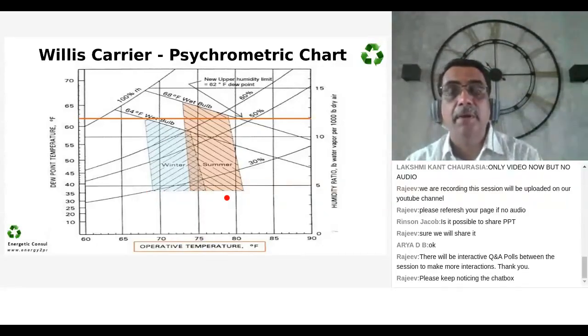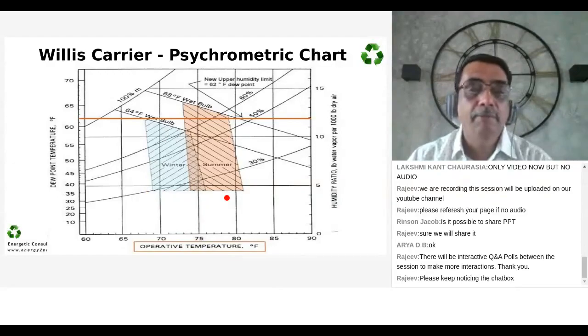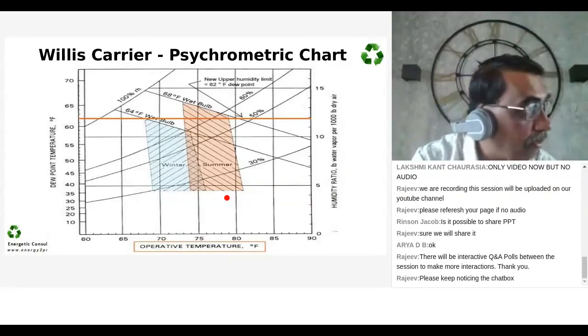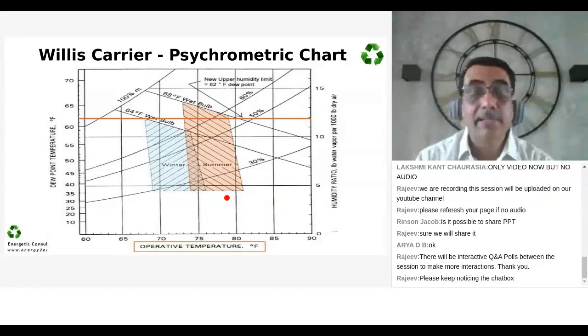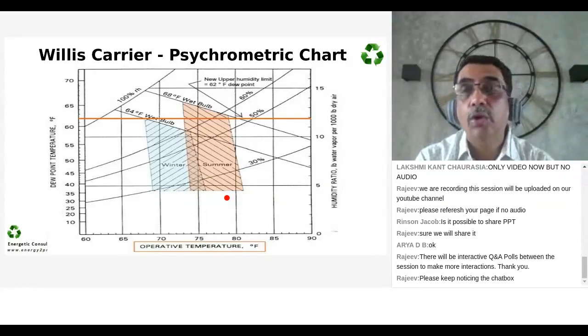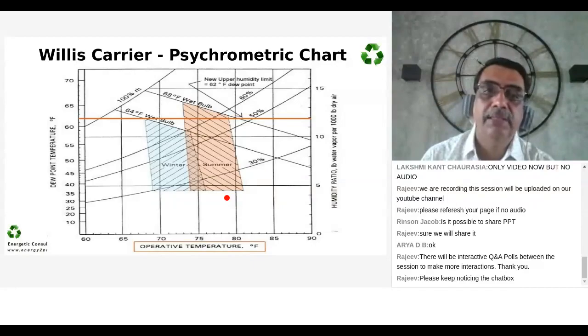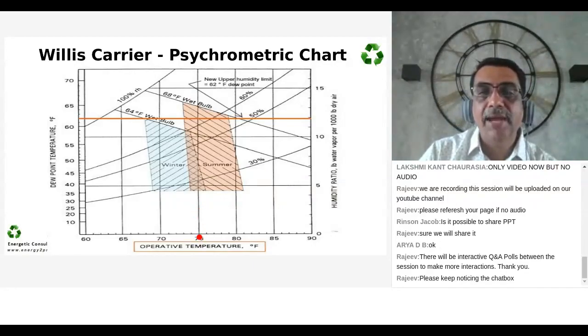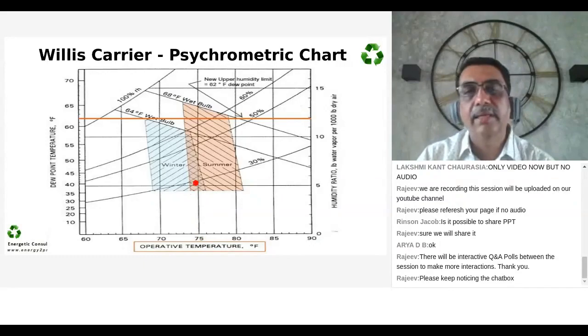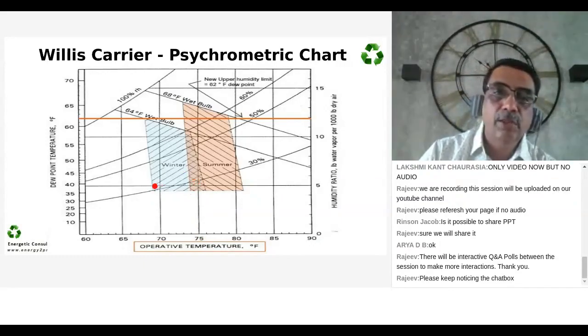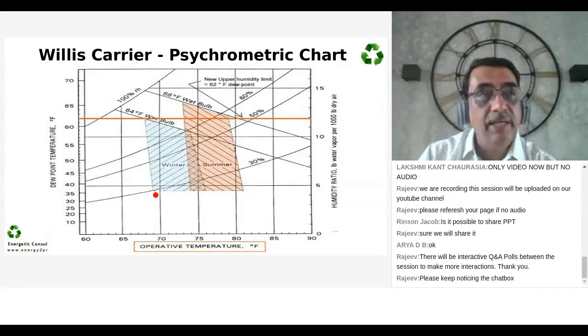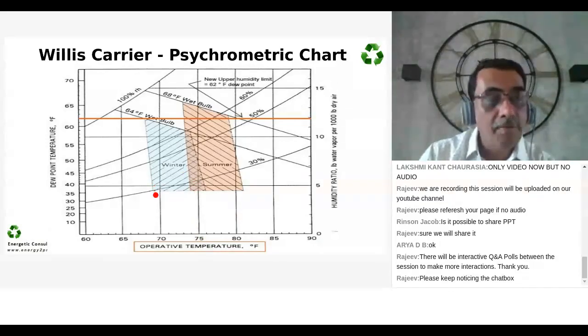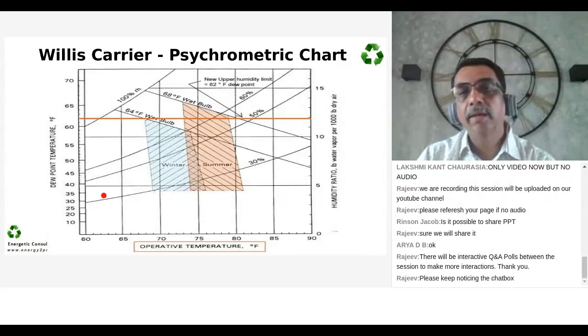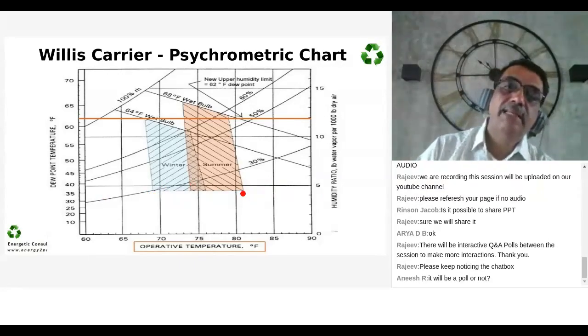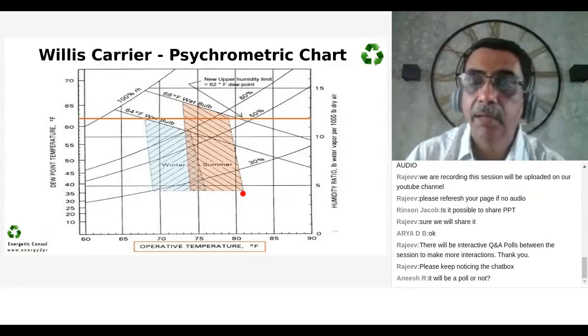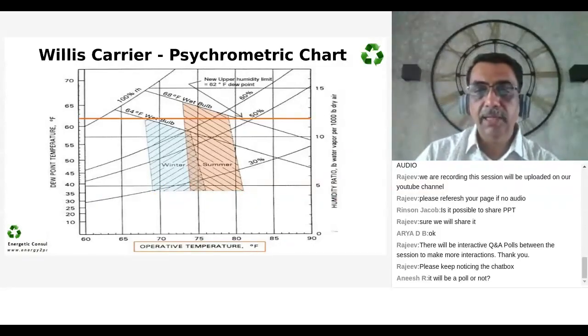Which means that a person is going to be more comfortable at lower temperature in winter and higher temperature in summer. And you see what we do at home, we set temperature to 18 degrees centigrade on a hot summer day. Now, that's not correct because human comfort is not going to be at lower temperatures. 75 means the mean, which is around 23 degrees C, it goes as low as 68, which means that even at 20 degrees C, a person can be comfortable during winter, and at 27 degrees centigrade, a person can be comfortable during summer.